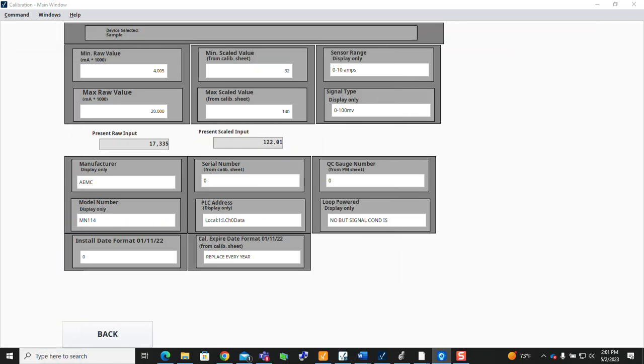And we're pretty precise. You're not going to ever get it exact. The decade box is calibrated. If you get within a tenth of a temperature mark, then we're doing well. Once you've done this, disconnect your decade resistor box, hook your thermistor back up, and you should be reading ambient temperature right here once we have this in. So I'm going to pause the video here real quick and we'll hook it up and make sure we're reading ambient.